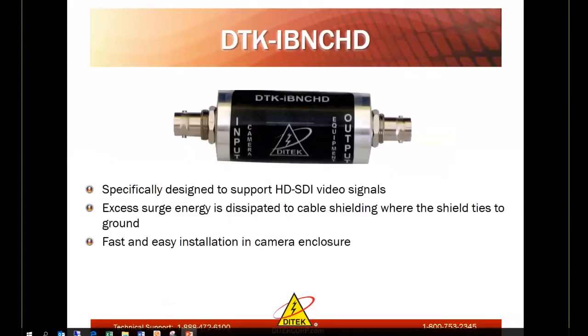The IBNCHD that we spoke about is an inline device that is used at the camera housing. The HD SDI is for HD SDI application only, and what that device does is reference the surge to the shield of the cable to reference ground. When you're using these inline protectors at the remote camera location, it is best to provide protection back at the head end with a ground reference surge protection device, so you can divert the surge from the shield to earth ground at that point.